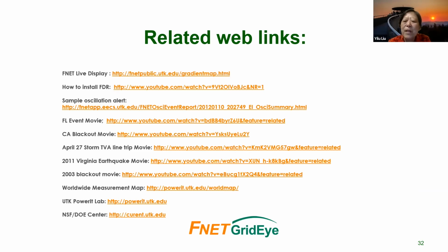There is one issue though: remember, the system protection may be set up for one-way flow. So if somehow the generator is still feeding the system without the awareness of the distribution grid, there could be a safety issue as well. You think the power is cut off, it's obvious you're out of power, but then somehow you're still feeding back from the individual source.